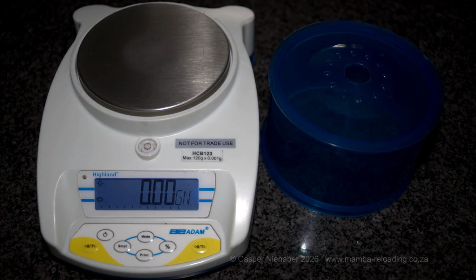Let's take a look at the HCB 123's parameter settings that can be adjusted by the user. I will only discuss the settings that I personally recommend changing. Adam's default parameter settings are generally well configured for most users, so there is no urgent need to modify them unless you have a specific reason. Do not adjust any parameters that are not described here unless you are completely certain of their function.